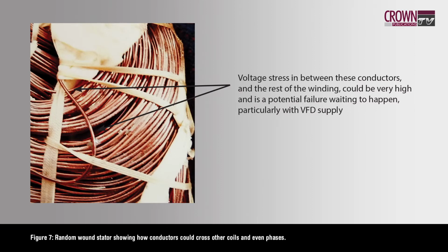But the other thing about the repairs industry is, if you look at photograph or figure 7, you'll see that sometimes the winders get wires crossing each other, and of course then it's more susceptible, because you now get high voltage between turns. Normally, random wire wound machines are random, and some of the turns get very close to the other turns, so you can get quite exceptional interturn voltages. And that is a particularly bad example.